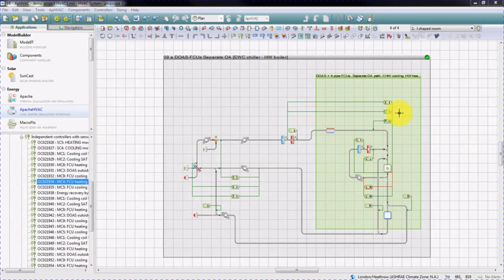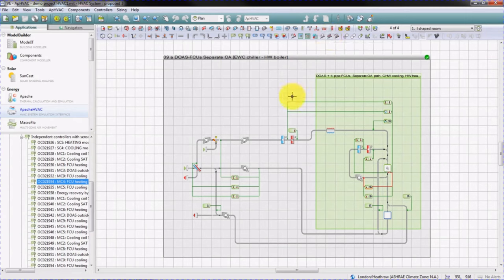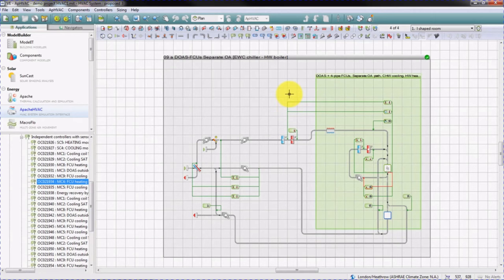Auto-sizing consists of two stages. In the first stage, ASHRAE room and zone level sizing calculations are performed to calculate flow rates, coil sizes, and plant sizes such as boiler capacities and chiller capacities. The coils and plants within the network are then populated with these sizes. Once all the data is in the HVAC network, it can then be dynamically simulated using Apache Sim and the performance of the system can be analyzed.